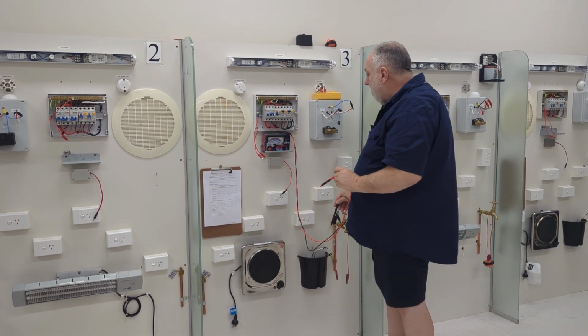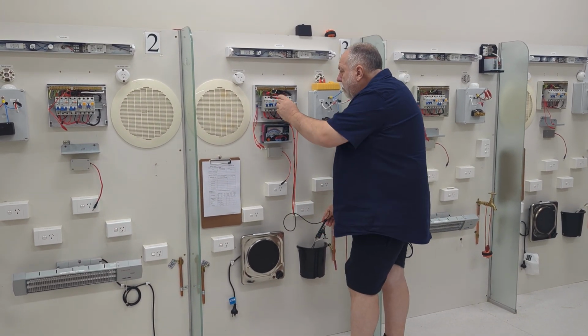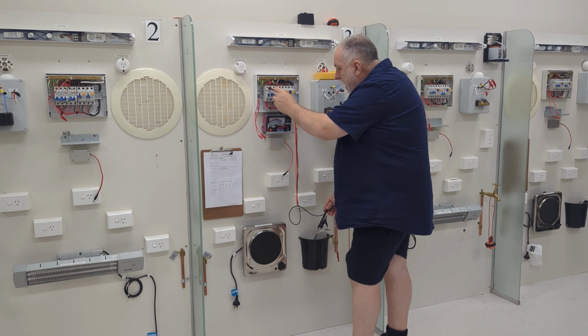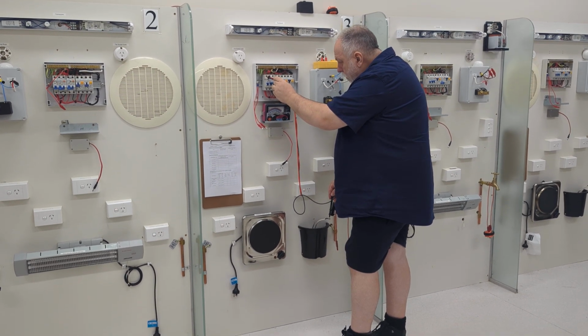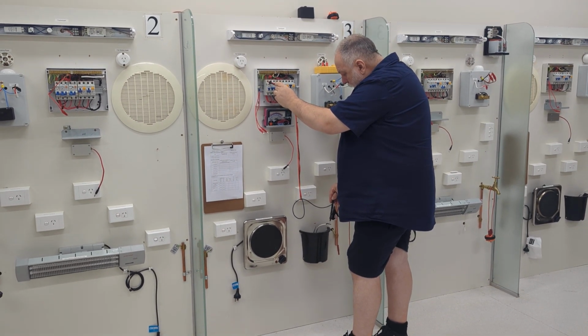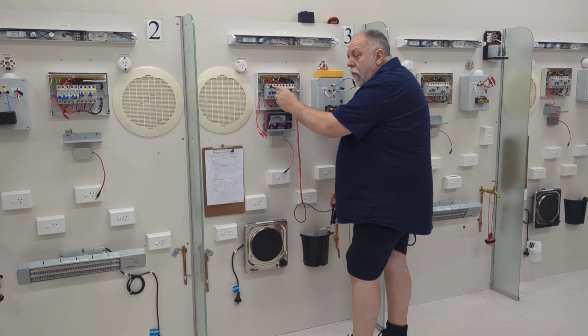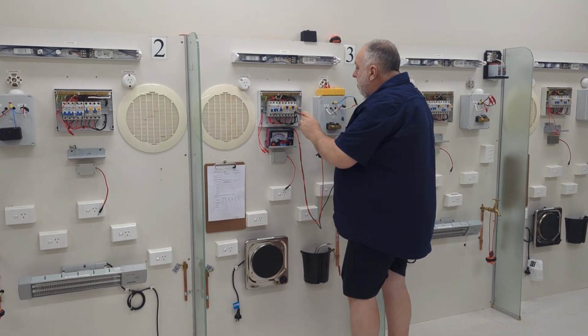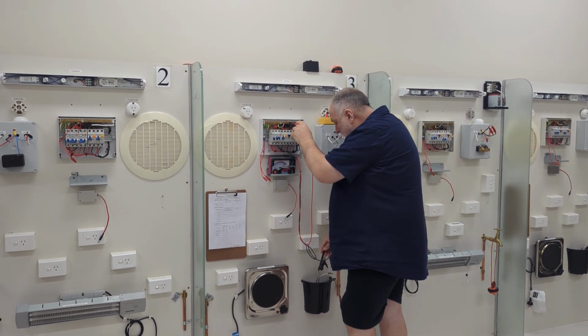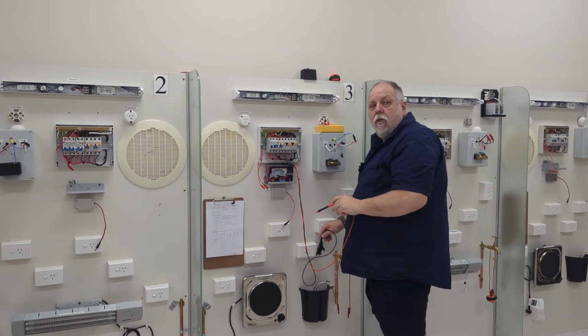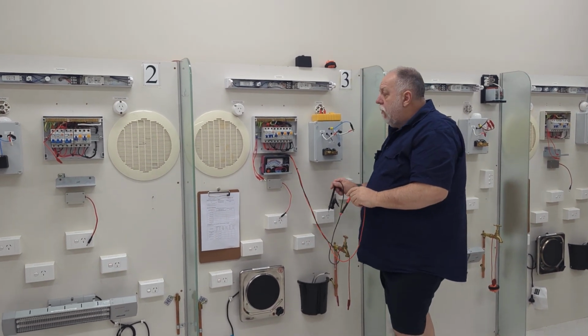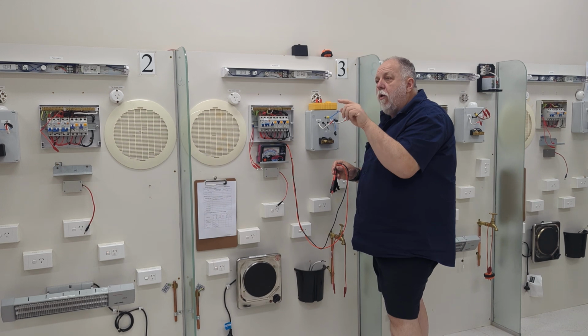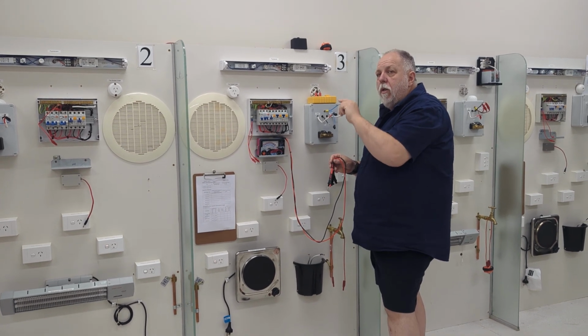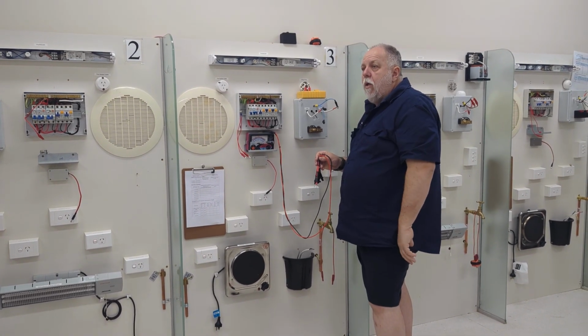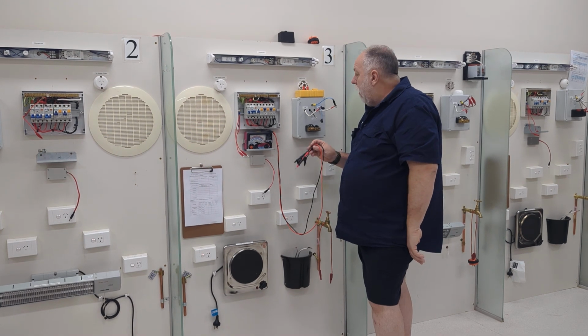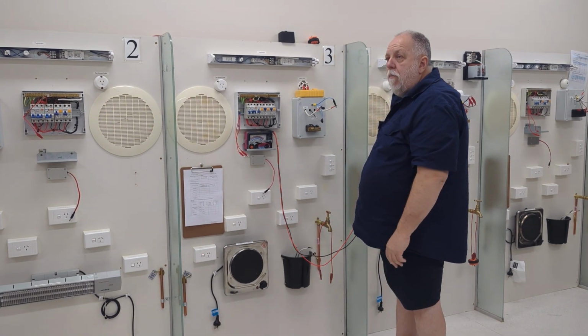So I'm going to go from here, the top. I'm not getting nothing. Let's just go to the neutral. Okay, so I've got my polarity switched. Okay, I'm now going to do the neutral. Go to the active. So my polarity is actually switched on the mains. So what I have to do is write on both of them that they both failed, but I would write a little comment that the mains are transposed. Okay, and that can quite easily be fixed in the back of the meter box.